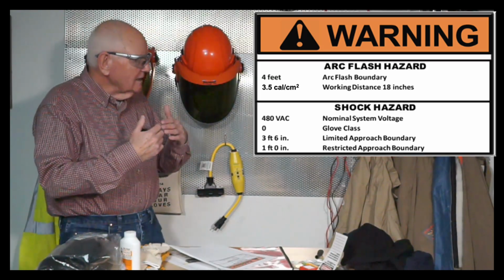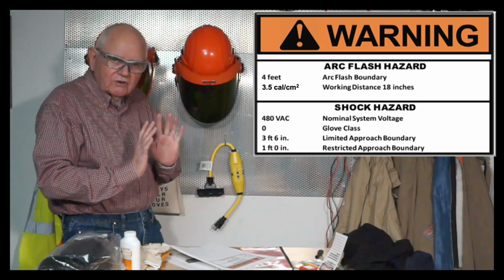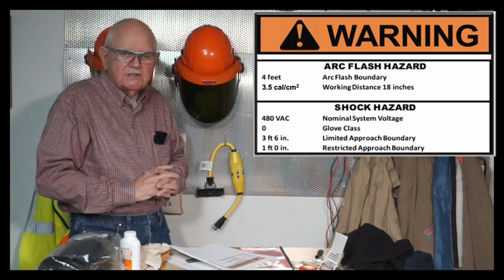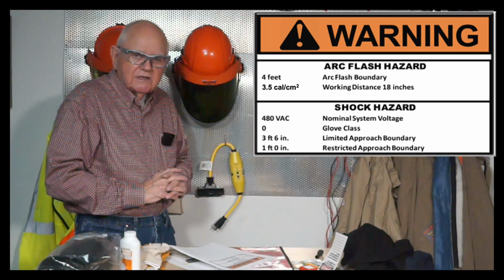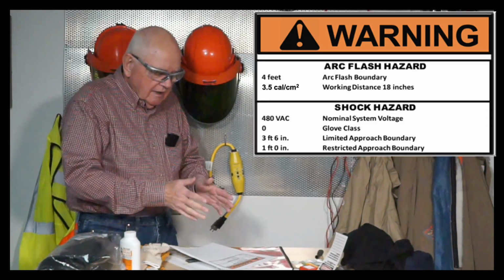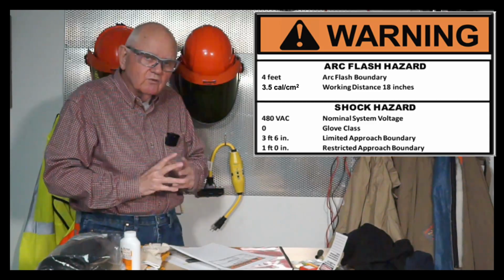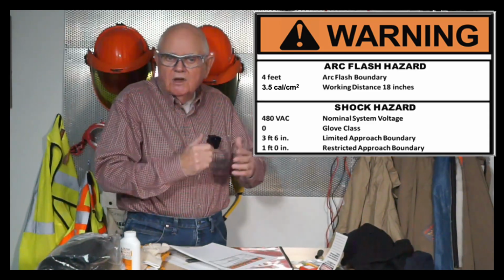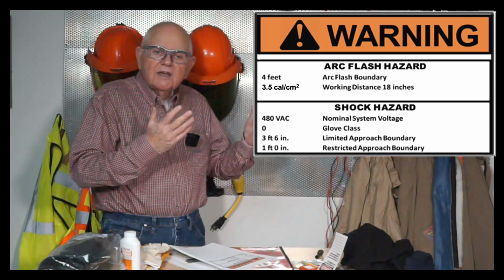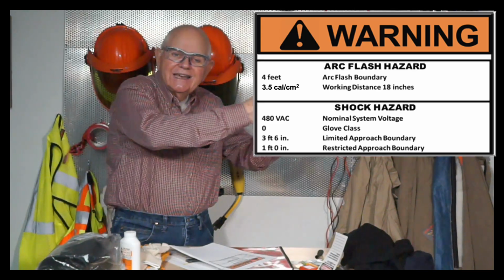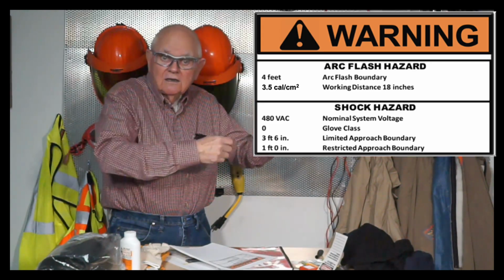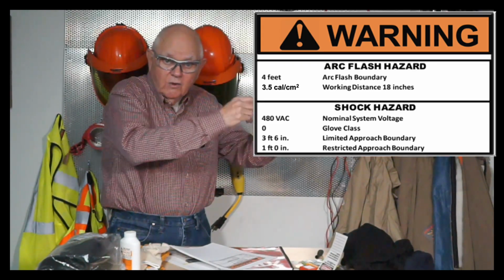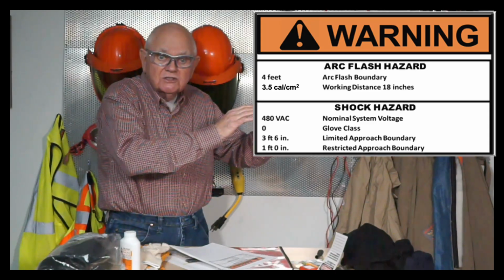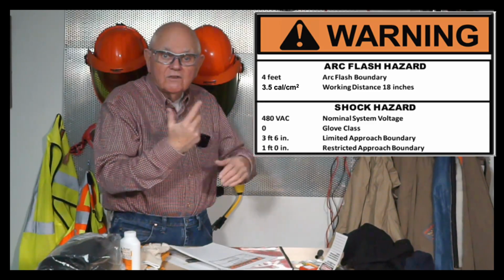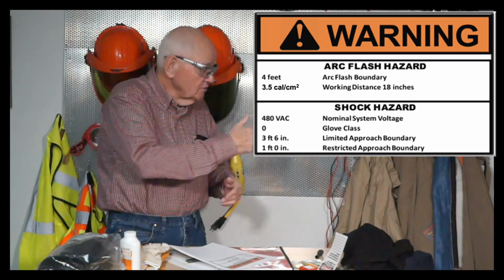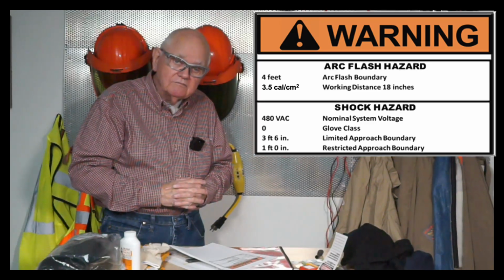So I don't want any unqualified person, certainly, to get within 3 feet 6 inches because I don't want them to get a shock. Now, the restricted approach boundary is 1 foot away, 1 foot 0 inches, 12 inches. Okay. So what's that based upon? Anything that I'm going to take inside of that restricted area within 12 inches of those live energized parts has to be insulated. Whether it's gloves on my hands, insulated tools, test leads, whatever it is.